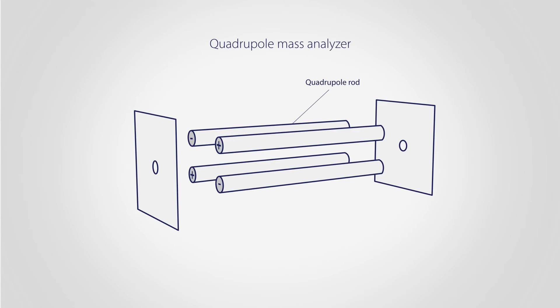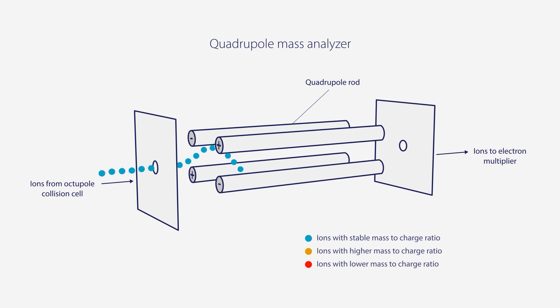The oscillating field applies an oscillating force to ions moving through the quadrupole. Their resulting trajectories depend on their mass to charge ratio and the magnitude of the voltages on the rods. For given magnitudes of AC and DC voltage, only ions with a specific mass to charge ratio will have a stable trajectory and can travel down the length of the quadrupole to reach the detector.